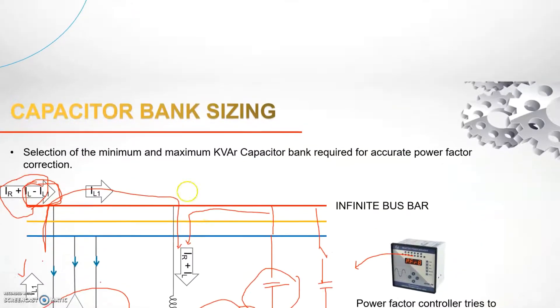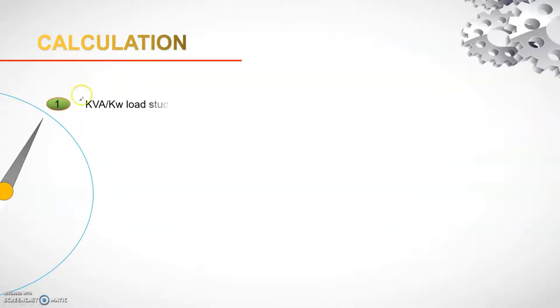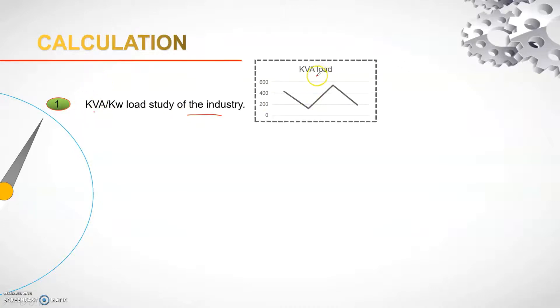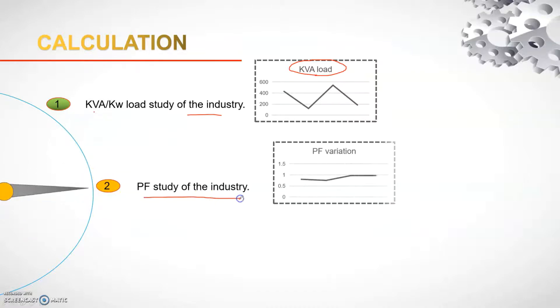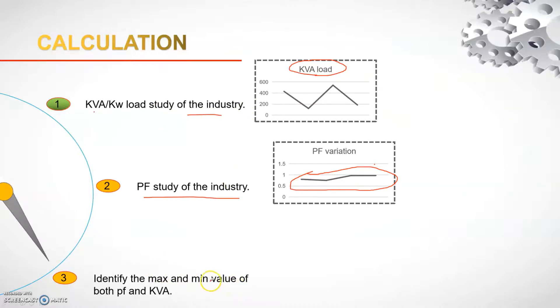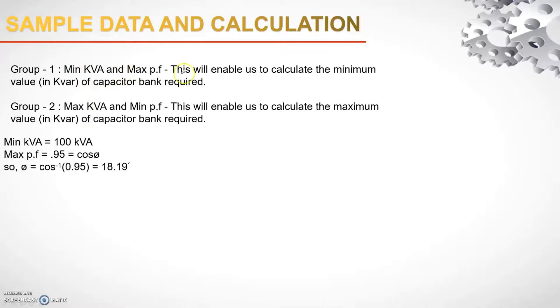For the calculation we need two pieces of data: first, the kVA or kilowatt load study of the industry, obtained from the watt meter; second, the power factor study, obtained from the power factor meter. From these two data sets we identify the maximum and minimum values of both power factor and kVA. Minimum kVA and maximum power factor are used to calculate the minimum capacitor bank KVAR, while maximum kVA and minimum power factor give the maximum total bank KVAR.